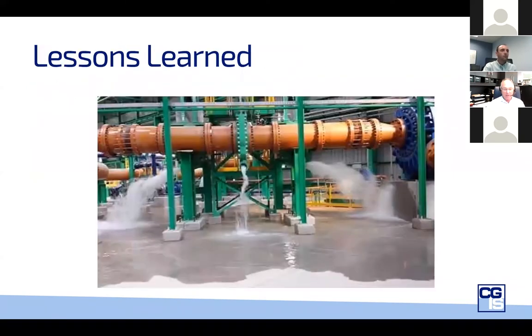Here is another aspect of a problem. This particular push-through knife gate valve is actually a very well-made product that tested zero leakage at the factory. But because of the thickness of the gate and the stress on the sleeves, the valve in the open position was producing free discharge — what we call free discharge of the process fluid they were trying to fill a 200-kilometer pipeline in Morocco with. In Morocco it's a desert; they don't have a lot of the water they want to fill the pipeline. So again — not a bad valve, an incorrect valve that might have tested to zero leakage but isn't accurate or meaningful in this application.